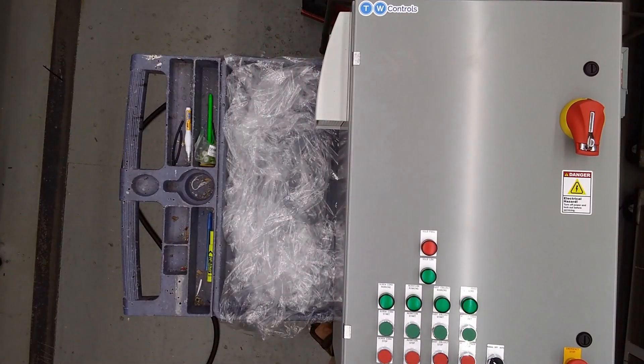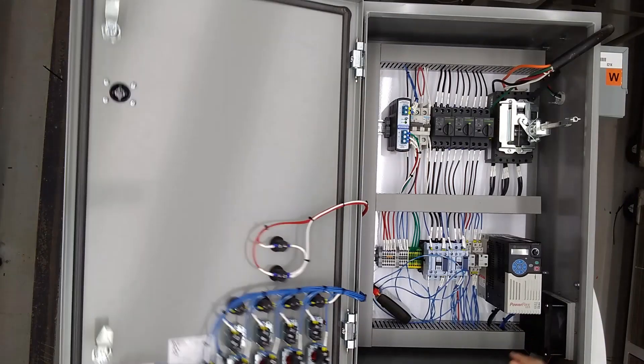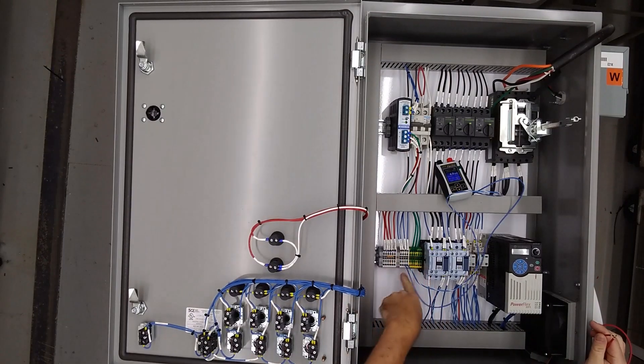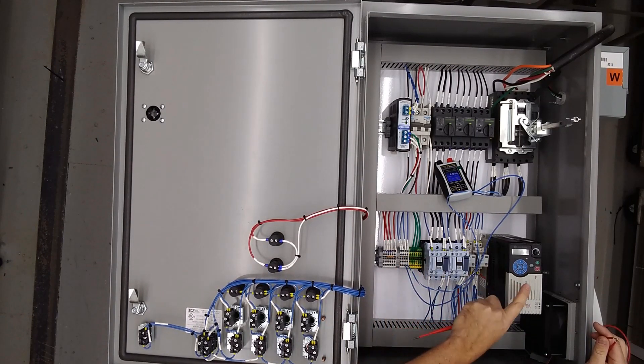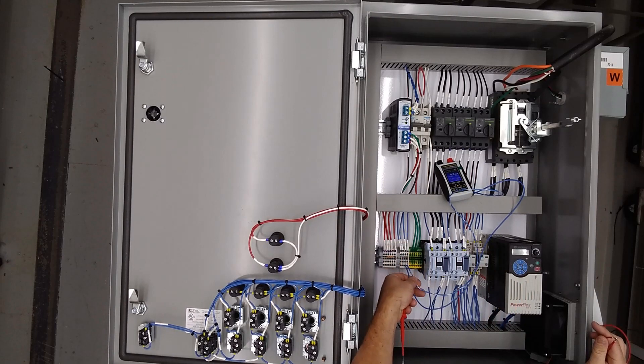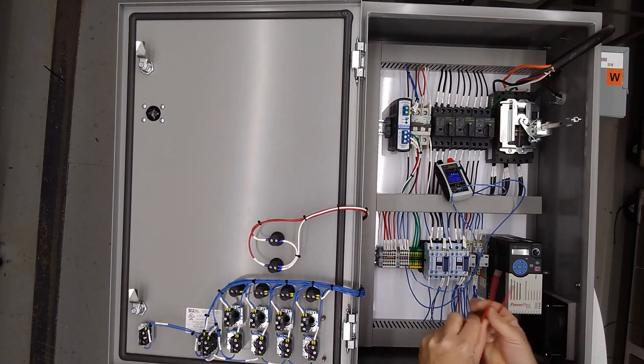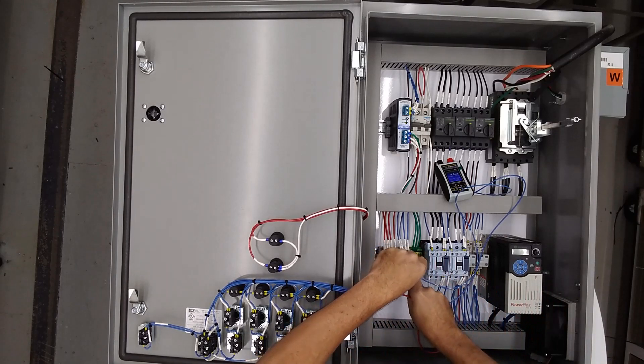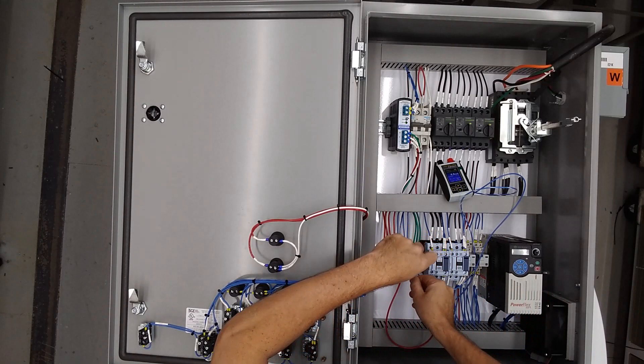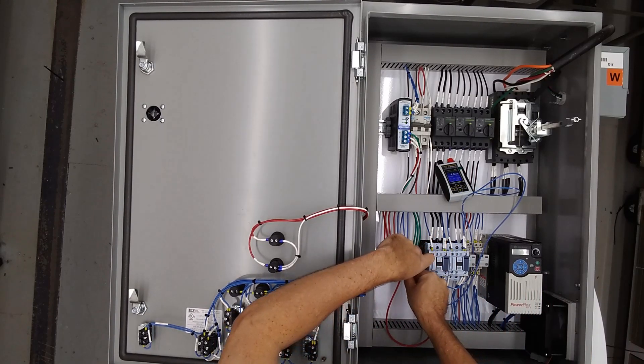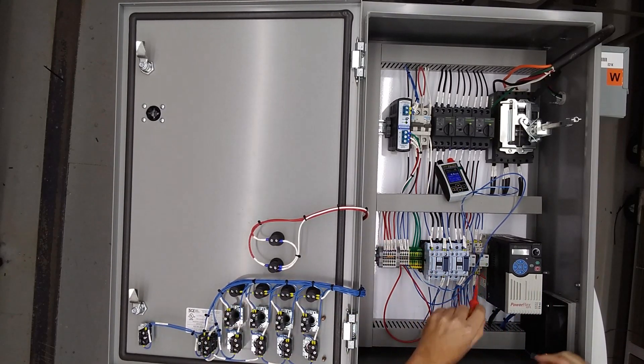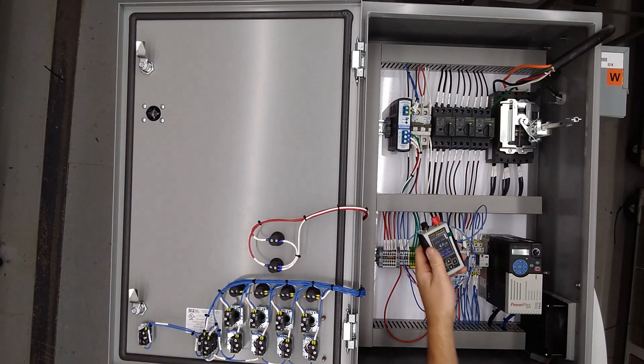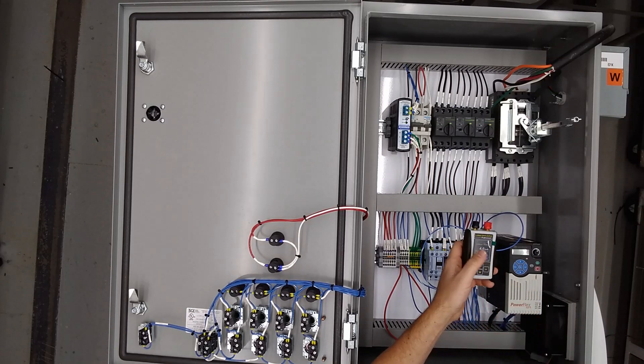We can press the stop button and now we'll switch to auto. Then with an auto mode, you're going to use terminals seven and eight. You'll put your contact closure there to run the drive and your four to 20 milliamp is going to go between nine and 10. So I'm going to put a jumper wire between seven and eight. And you'll hear the drive start. You can also see the relay pull in right here. And then the speed will be determined by a four to 20 milliamp signal.